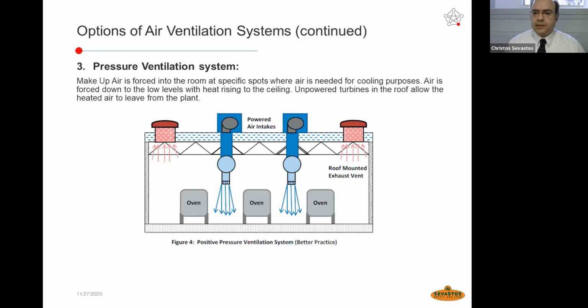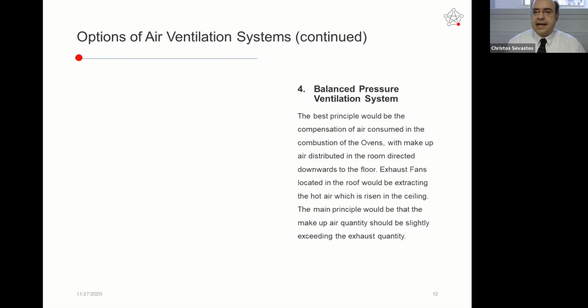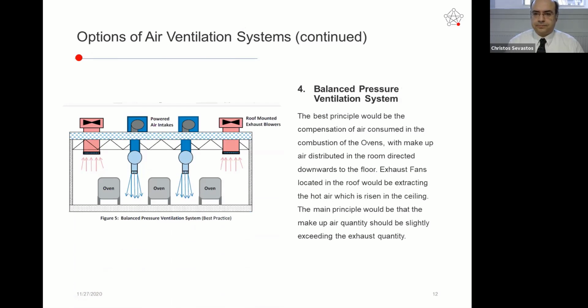And of course, we have roof-mounted exhaust vents with which we are extracting the heat. Those positive pressure oven rooms are considered to be better designs. The most efficient now is a balanced pressure ventilation system. The best principle would be the compensation of air consumed in the combustion of the ovens with makeup air distributed in the room, directed downwards to the floor.